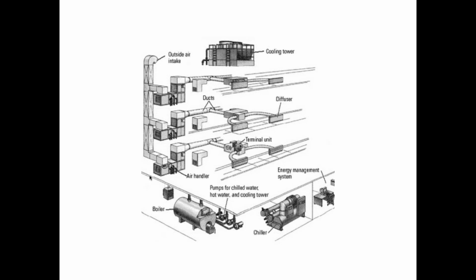And what about for heat? Well, for heat, we put a boiler in the building, make hot water, and we pump that water to another coil in each one of those air handlers, and we call that a hot water coil. Sometimes we use steam, but a lot of times in a building like this, they'll use hot water. Sometimes we only use one coil, and in the summertime, they'll put cold water through that coil, and in the wintertime, they'll put hot water through that same coil. Let's call it a dual temperature coil, right? So instead of pumping Freon all over the place, you're pumping hot water and cold water.